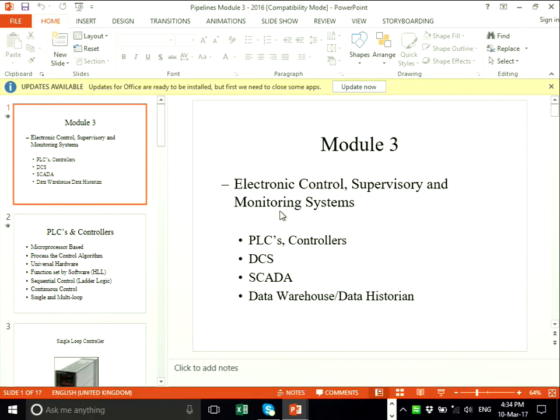That's one of the very reasons why you don't put these sort of things in the safety loop, because if the data link goes down, what happens if something's gone wrong in between? I know. I think filters were a bit of a worry on that at times, because if you have a problem where a filter bursts, you can monitor filter DP and have an alarm that says the differential pressure across the filter as it starts to get blocked is going up. But if it bursts in between scans, you miss out.